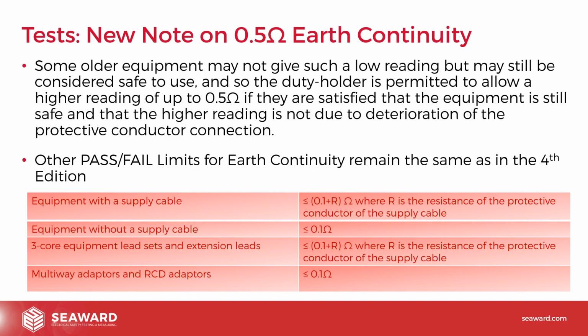and where it covers some, and I say some, it's a very, very small amount of old equipment that may actually give a higher earth continuity reading, and that's because it was designed to an older standard. And that was what it was designed to do. So the actual standard it was created to originally, and we're talking equipment from a long time ago, may not meet the 0.1 plus R. Not because it's deteriorated, but because of how it was designed in the first place, the cable sizes, the lengths of cables, things like that. So going back through the old product standards, there is a small section of equipment that may have higher readings up to as much as 0.5.